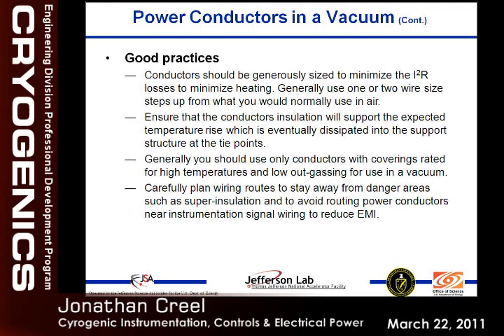How do you check on the job that you got the right wire? You mean for a vendor or for something we're doing? If it's something we're doing, I know what it is. If it's something a vendor's doing, the only way you can do it is by telling them in writing what they have to use, which is what we do. And then when you go out to do your inspection of the equipment, when you're doing your acceptance, you need to check it and make sure.